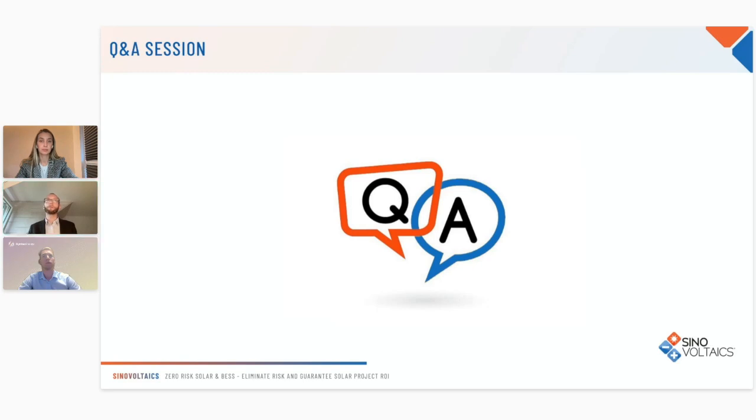Thank you, Arthur. And one last question from David is, how important is the selection of the OLTC manufacturer in a high voltage transformer? I guess a question to you, Arthur. Yeah, again, short answer, yes, it is important. It's a component that is highly under stress as part of the life of the transformer. And I would ask for the BOM of the transformer to check what kind of OLTC is included there. And I would also be careful about the OLTC suppliers and see if there are any spare parts that could be provided as part of the project.